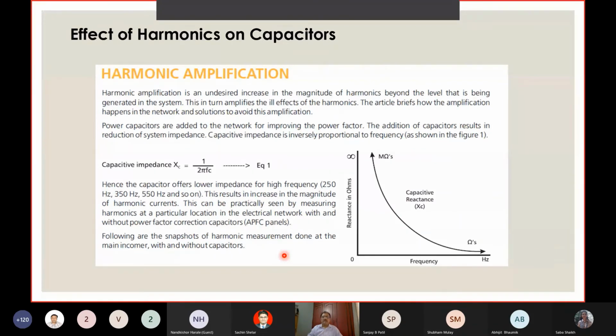That is the reason why the TDD limit is prescribed and it has to be reduced. When you reduce the TDD, automatically the THD voltage will also get reduced. And the THD voltage is a parallel branch activity. So it will spread from one branch of the network to another branch. So while it is happening, the current, when it is traversing towards the grid, if it finds a low impedance, it's a low impedance path.